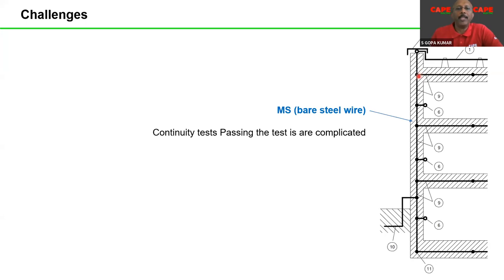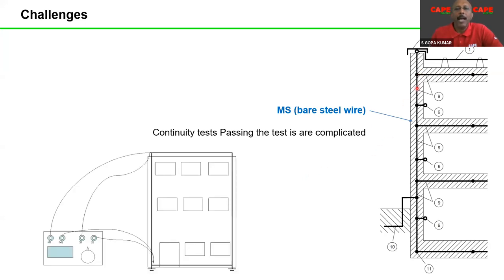In this case, out of our experience, what we are facing is that after finalizing, after making this installation, we are supposed to check the continuity resistance. In several cases, the continuity resistance check is failing. Using MS has that particular risk. Sometimes the required resistances are not achievable, probably due to corrosion or because the joints are not proper and so on. So MS material also has a risk. Please understand that. After casting your steel, or after construction, you cannot change anything. So if you wanted to make some modification, it is impossible.